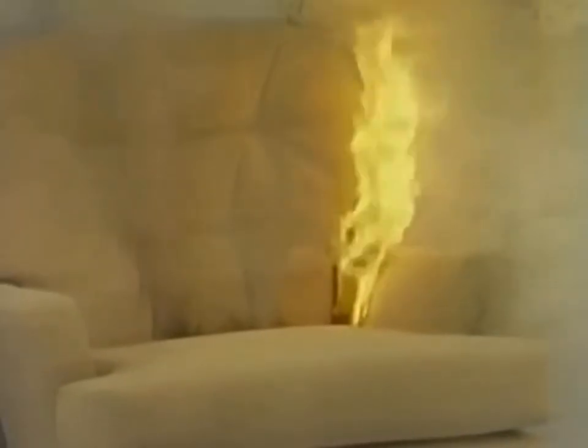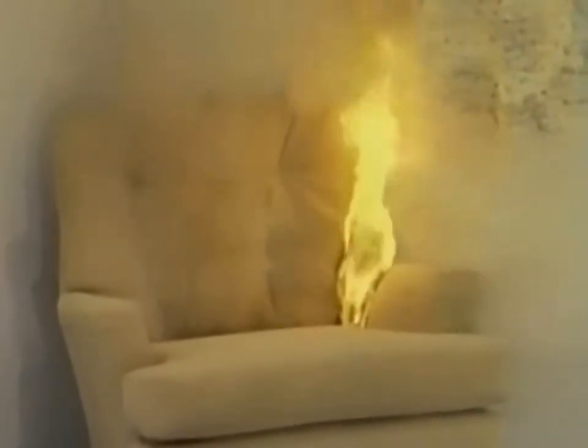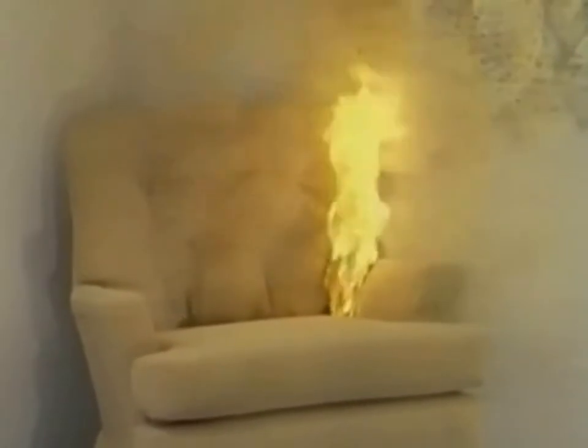Right now, we have a small flame. It is rapidly progressing into a substantial fire. As we noted earlier, the heat from the fire is producing combustible and toxic gases from the burning chair. A smoke detector has been placed just outside the room. The fire has now given off enough smoke to activate the alarm, telling occupants to make an immediate escape.